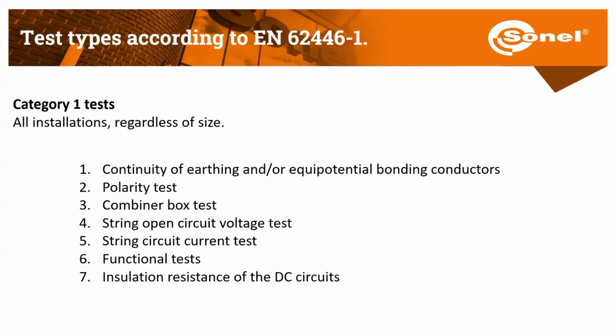We have three types of tests in a PV system, which are described in the 62446 Part 1 standard. All installations, regardless of size, should have category 1 tests. So we have to make continuity of earthing and equipotential bonding conductors, polarity test, combiner box test, string open circuit voltage, string circuit current test, functional test, and insulation resistance of the DC circuit. We will talk about these tests in a minute.